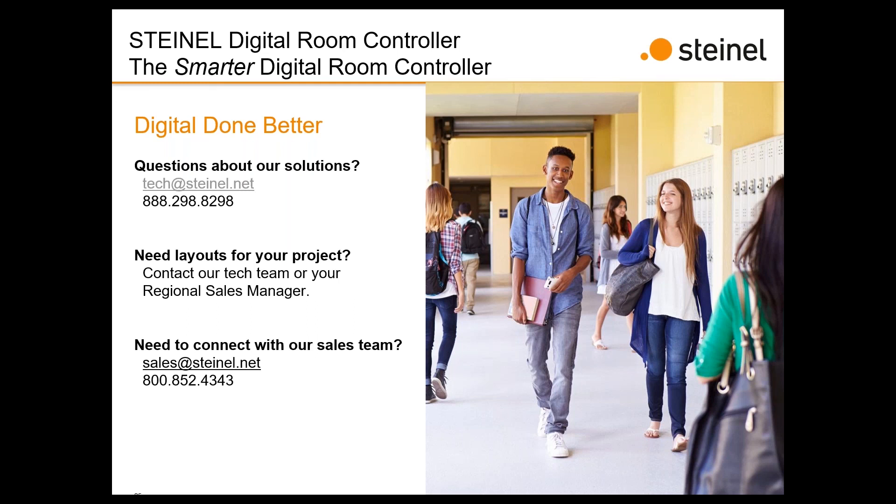Can this be used for fire alarm or security input for the whole system? There's a contact input — previously called the time clock input — that can be used for various other things, one of which can be a fire alarm. When programming the app, you create a sequence of operation for when that contact closure happens: for example, lights go to full bright, switches are disabled, occupancy sensors are disabled. Whenever the device receives that input, it performs the action you've created.